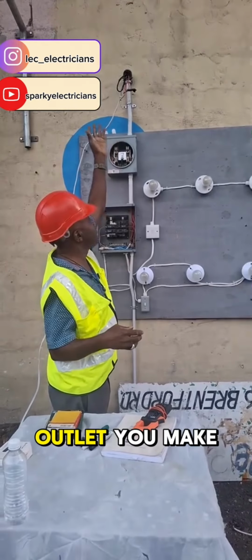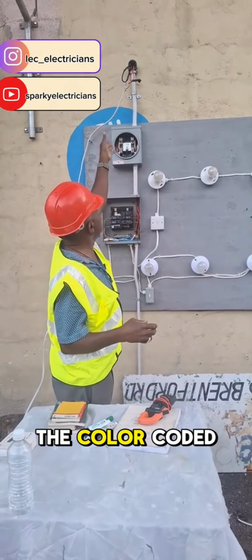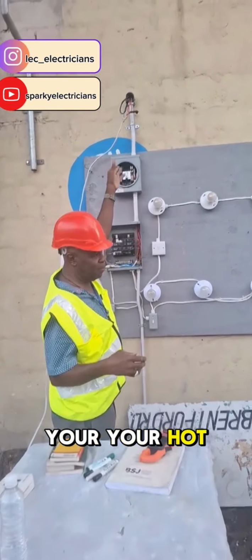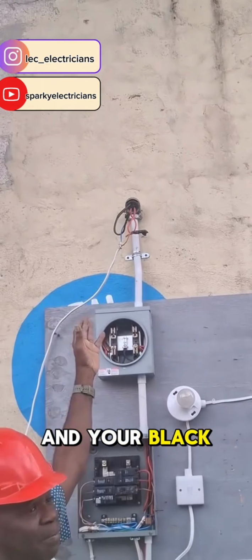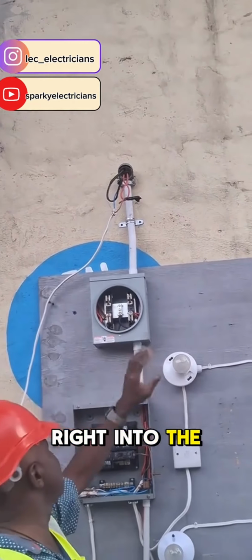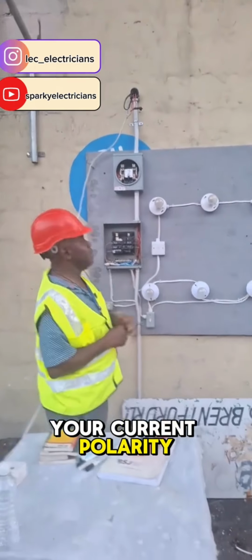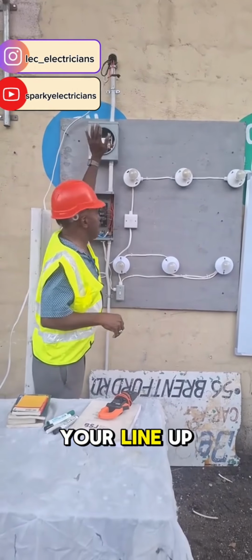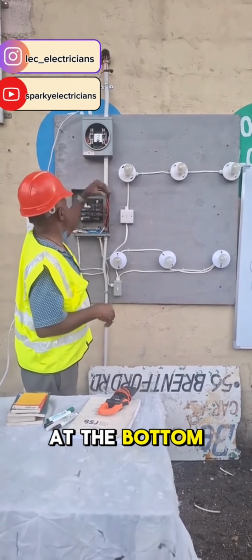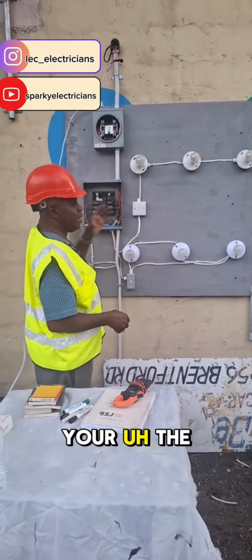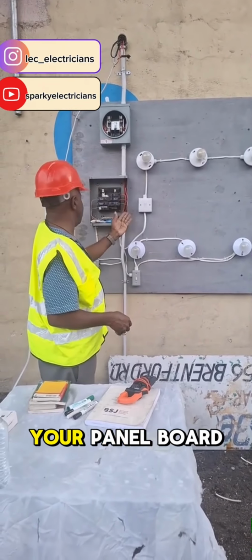The supply, the two outlets. You make sure your conductors are color coded, the red for your hot wire and the black for your neutral, right? Maintain the correct polarity at the meter socket here: your line at the top, the load at the bottom. Terminal coming to your panel, your distribution panel, your panel board.